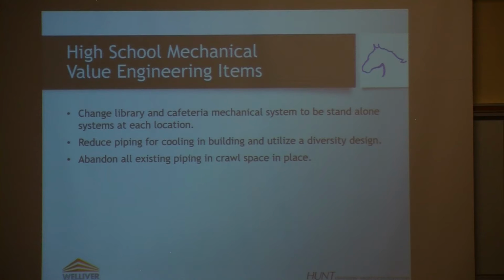The next line item is reducing piping for cooling. Basically, we designed a system that could run air conditioning in every single space in the building that it's provided to — 100% of spaces with air conditioning. That's how the project was originally designed: you could air condition all your classrooms, the gymnasium, the auditorium, and the cafeteria, all at 100%. That was the approach.